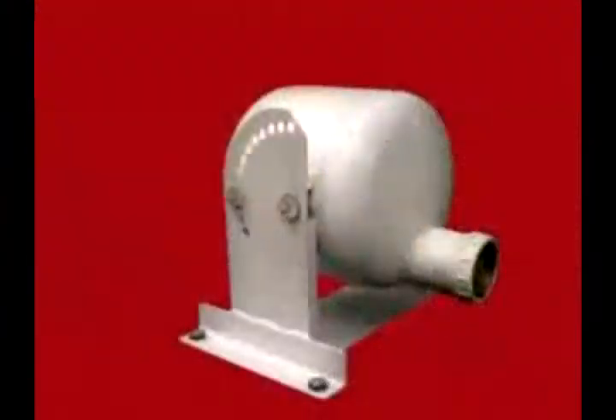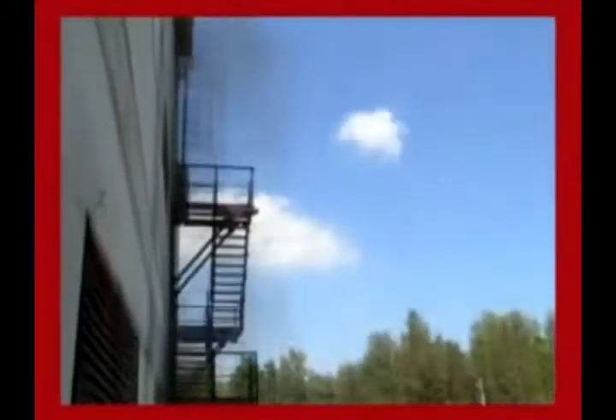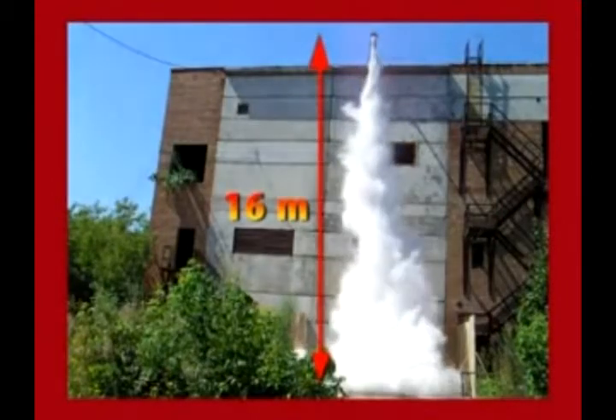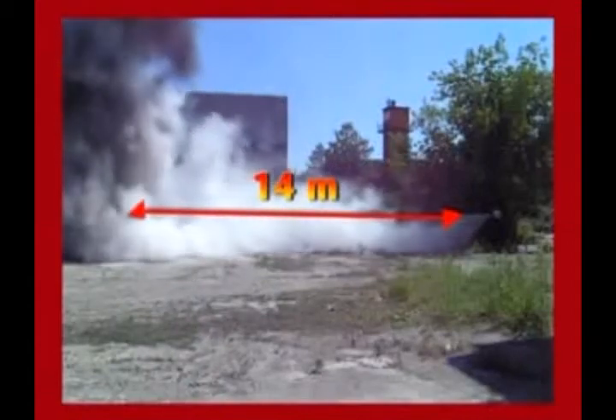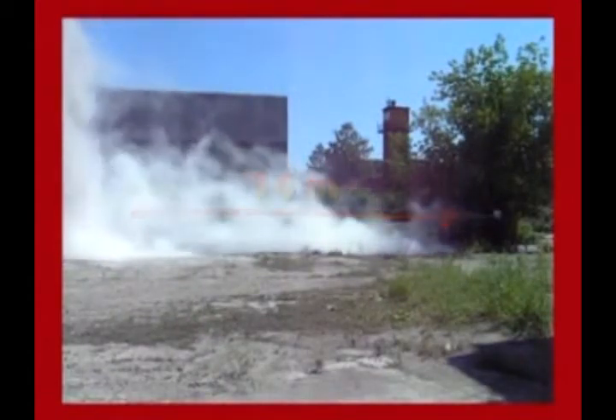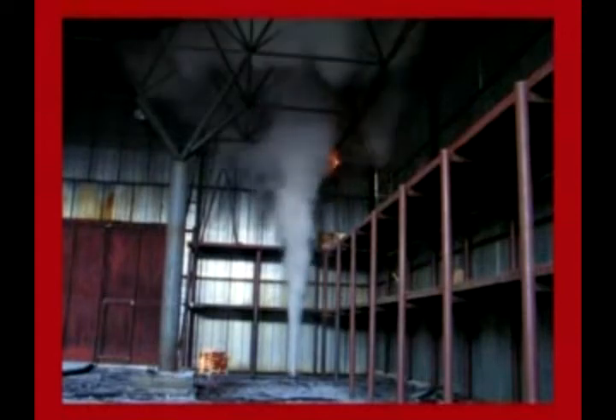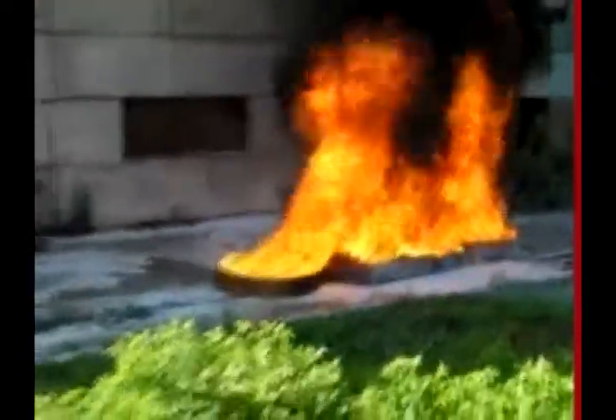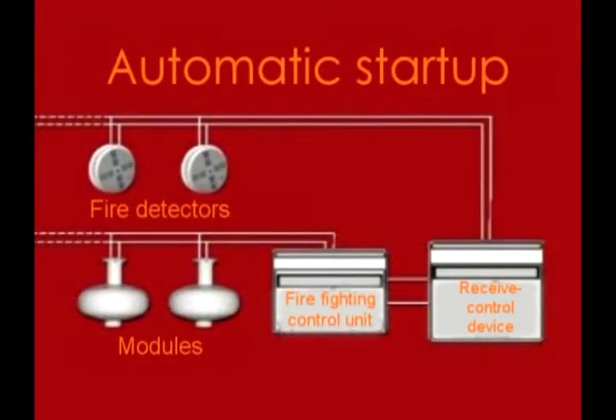The second has an adjustable angle of extinguishing powder discharge and provides suppression of fires on an area of 80 square meters with a height of up to 16 meters, up to 14 meters in the horizontal arrangement of the module. Creating modules with different directions of extinguishing powder discharge eliminates the formation of shaded areas that are inaccessible to direct exposure to the extinguishing agent.